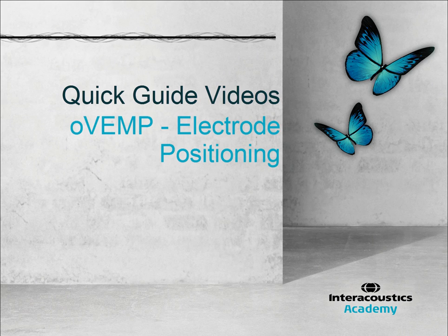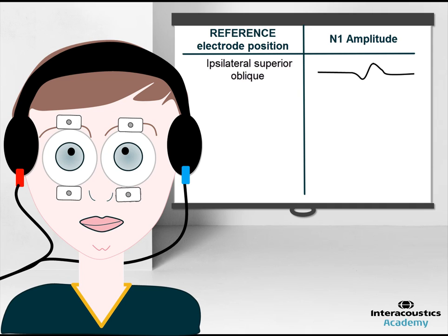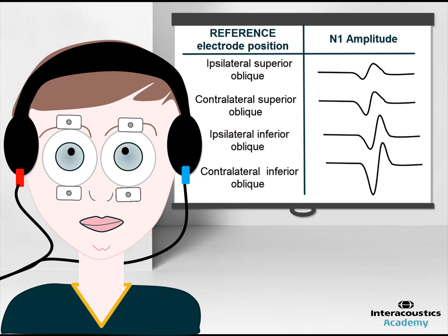This quick guide video provides an overview of how to position the electrodes when performing OVEMP testing. In 2007, Todd et al. demonstrated that OVEMPs can be recorded from several different electrode sites, but the largest N10 amplitudes are obtained when recording from the contralateral inferior oblique muscle to the ear which is being stimulated.